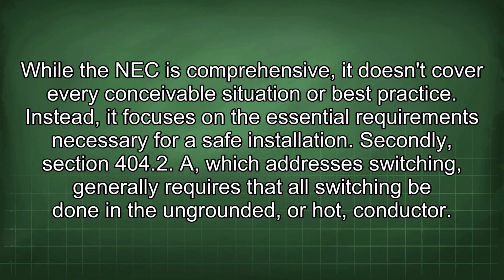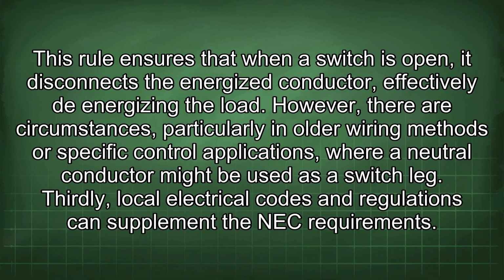404.2(A), which addresses switching, generally requires that all switching be done in the ungrounded or hot conductor. This rule ensures that when a switch is open, it disconnects the energized conductor, effectively de-energizing the load. However, there are circumstances, particularly in older wiring methods or specific control applications, where a neutral conductor might be used as a switch leg. Thirdly, local electrical codes and regulations can supplement the NEC requirements.